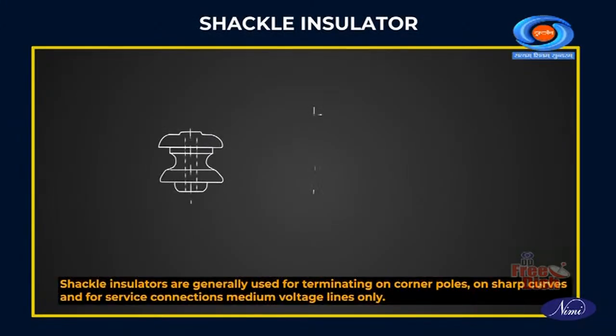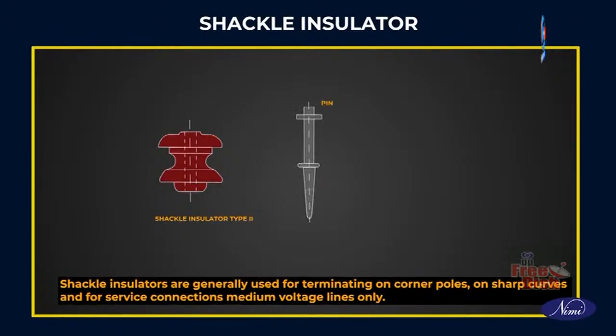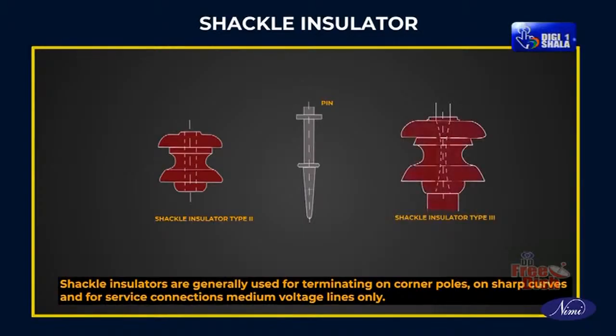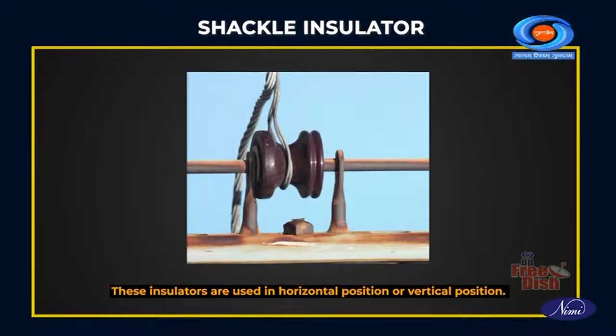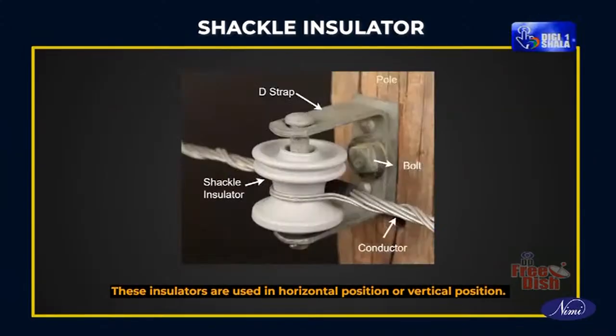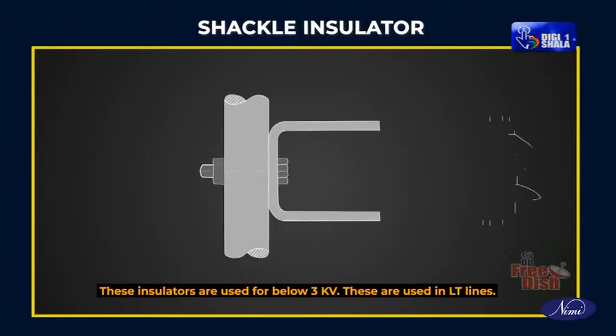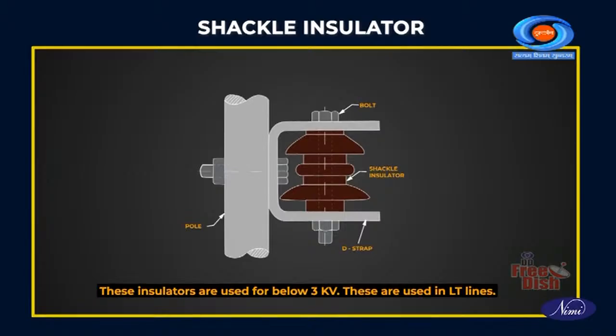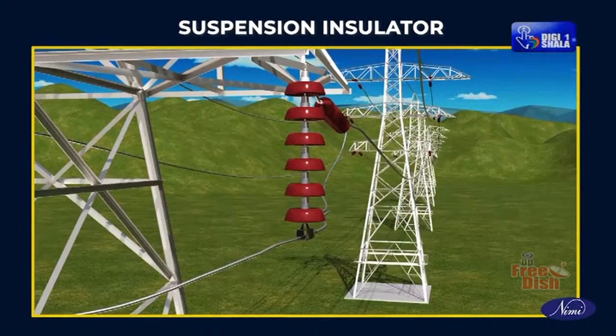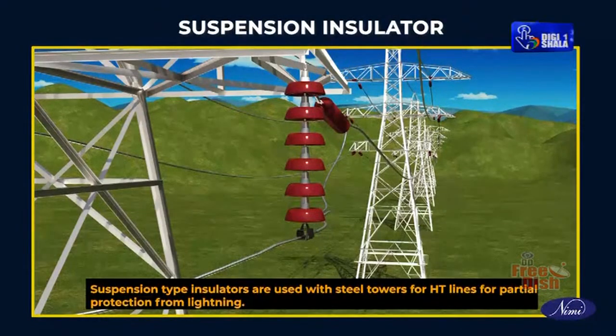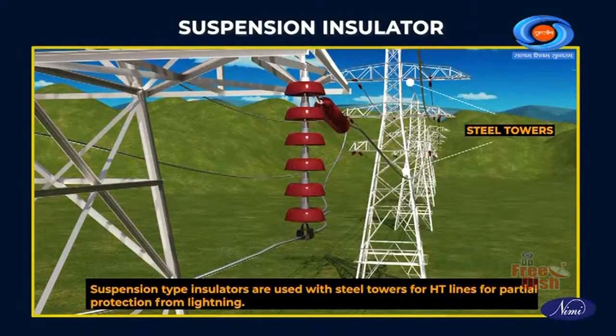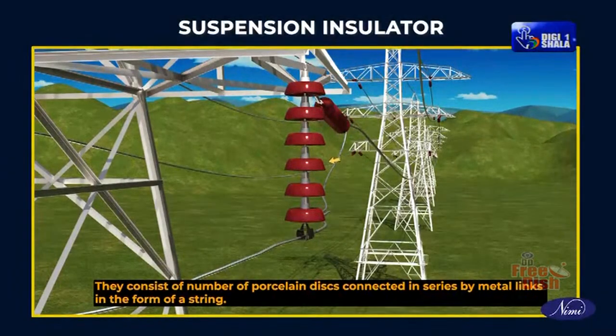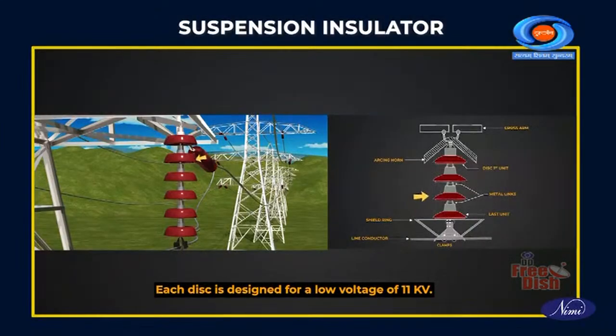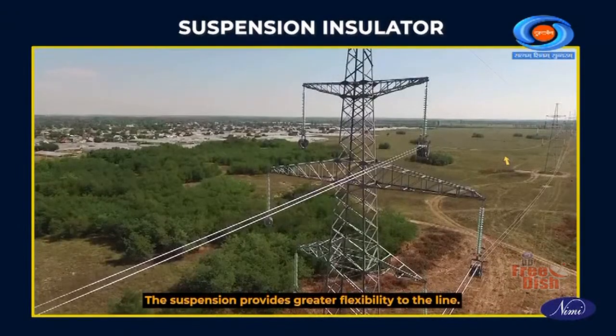Shackle insulator. Shackle insulators are generally used for terminating on corner poles, on sharp curves, and for service connections, medium voltage lines only. These insulators are used in horizontal position or vertical position. These insulators are used for below 3 kV. These are used in LT lines. Suspension insulator. Suspension type insulators are used with steel towers for HT lines for partial protection from lightning. They consist of a number of porcelain discs connected in series by metal links in the form of a string. Each disc is designed for a low voltage of 11 kV. The suspension provides greater flexibility to the line.